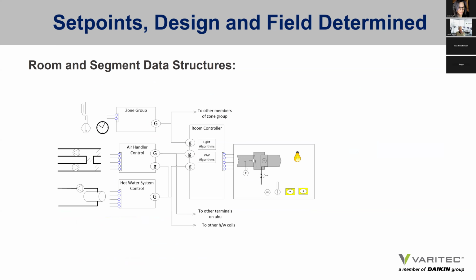So to give you an idea of the actual structure, here's a wiring schematic that I drew from Siemens' presentation, and it might offer some visual clarity to what we're discussing. If we look at the actual room zone, the room VAV box with temperature airflow sensor, you can see that it is a device that regulates conditioned air to a space at a volume necessary to maintain a thermostat condition.